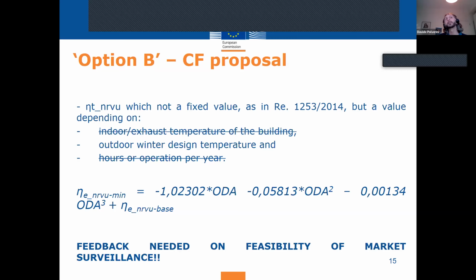I can imagine that this, seen from the eyes of, let's say, an academic, is perhaps not the optimal because it's a simplification, but we must bear in mind the usage that we make of this formula, so for regulatory purposes. And that's our current proposal, the one which we discussed in February last year. So the aim would be to basically have a new requirement on the heat recovery efficiency dependent on where the product would be installed, because depending on the geographical location, we would have the variation of, obviously, the outdoor winter design temperature.